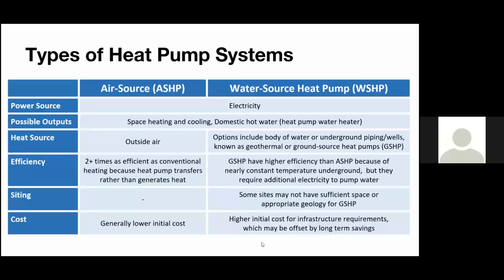And then in terms of capital cost, because of course this comes up a lot. Usually one of the reasons the air source heat pumps are getting so much traction for all electric buildings is because they're usually a lower capital cost. It's typically just an air source condenser on the roof or on the side of the building, refrigerant lines in the building, some fan coils, and that's kind of all you need. Whereas the water source heat pumps need to handle the water side geothermal loops, any wells, pumps, all those additional components. Of course, it's a different story if there's existing infrastructure as well, which we'll touch on a little bit later.